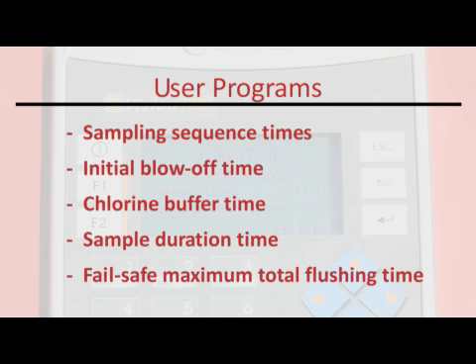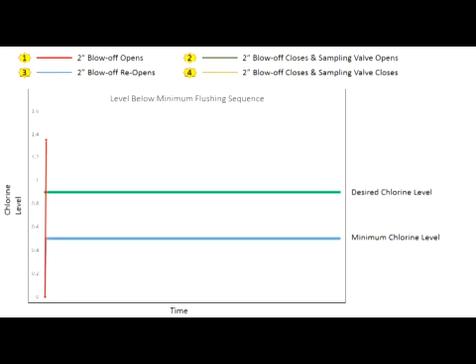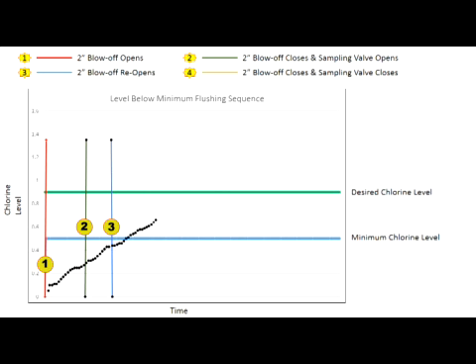Once this information has been inputted, the unit will automatically maintain residual program parameter levels in the following order of events. At the programmed sampling time, the unit will begin with the initial blow-off to remove old water and obtain a sample from the main, usually one to three minutes. Once the sample is obtained and analyzed, if the sampled water's residual level is below the program minimum chlorine level, the unit will begin to flush, all while continuing to sample. Once the sampled water's chlorine level reaches the program desired residual level, both valves shut off.